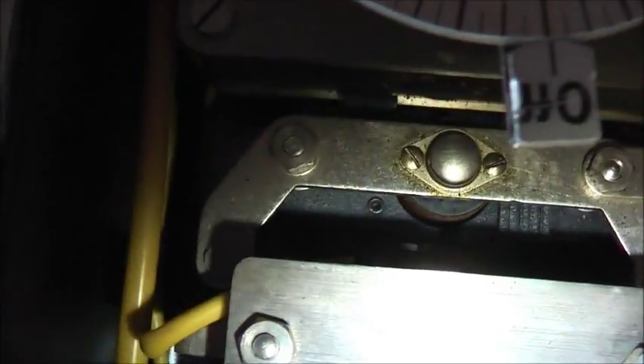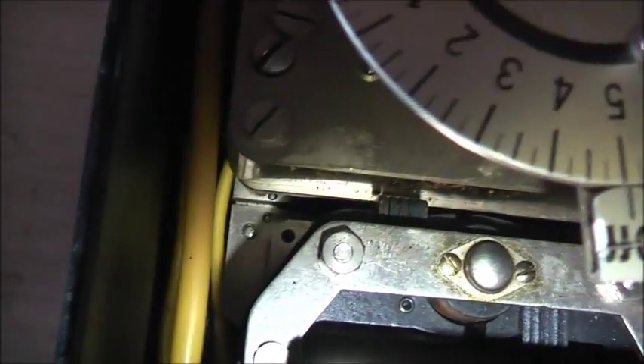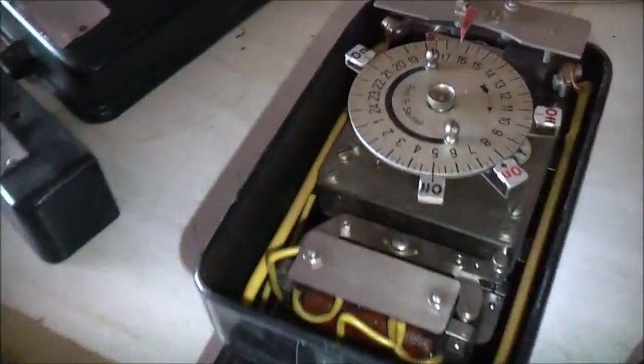Alright, let's do some quick checks. Motor wound up okay, no arm shorts. Earth - safety first - that's the earthing point there. I did an earth check and the chassis is completely earthed. Everything is working fine there.